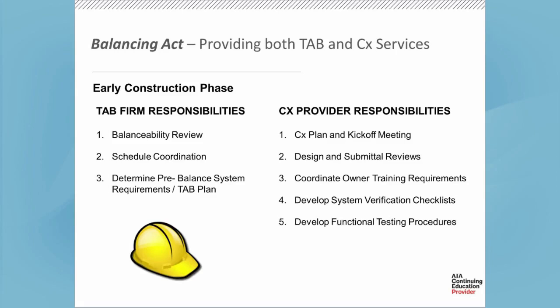This becomes very critical on larger systems, such as in healthcare and research facilities, where you have very complex systems that are not straightforward. Many times those types of systems are built vertically - meaning we have multiple floor systems that have to be tested - but the actual build-outs in the facility happen horizontally. So you can't turn things over to the tab firm the way you would traditionally do with smaller systems. That's just a good example there.